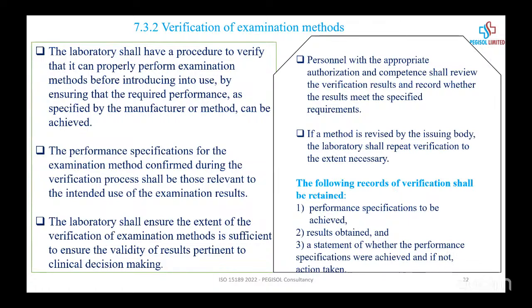That's an example of the laboratory shall ensure the extent of verification or examination is sufficient to ensure validity of the results pertinent to clinical decision making. That's why when you don't provide sufficient verification, before those things are authorized, they will tell you to go and get more samples that cover these areas, or go and get materials that cover this area.